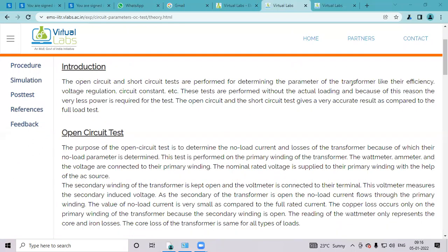So there is no actual load put on the transformer, just by open circuiting the secondary we are finding some of the constants, and by short circuiting the secondary we are finding some of the constants. After that we are able to calculate the efficiency and the voltage regulation. These tests are performed without actual loading, so the power required for conducting this test is less.